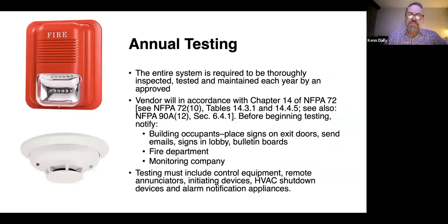And then annual testing, of course, is where every single device is functionally tested annually. And all of this is documented individually, guys. It's not like you get a receipt from a Happy Shady Pines fire alarm company that says, I came in and did everything in your building, $2,000. No, because first of all, invoices are not documentation of testing. And 2, you have to do every single device individually. So many of you know that your fire alarm report could be 10, 12 pages long because they list every smoke detector, every heat detector, every pull station, etc. And then they show the functional testing.